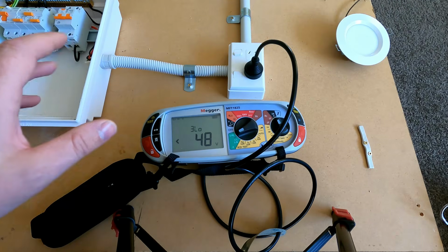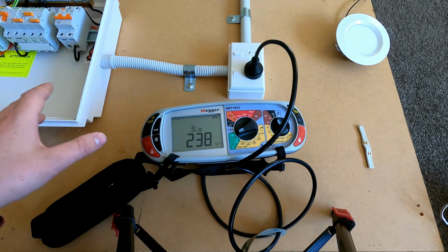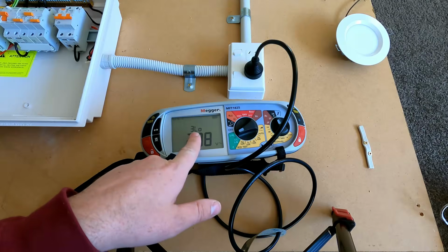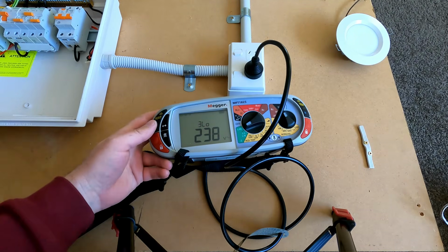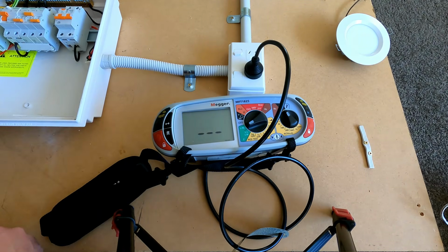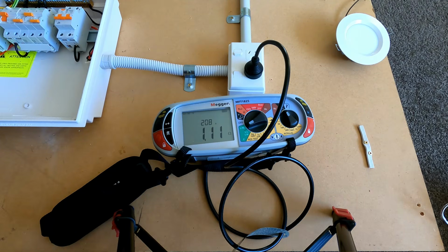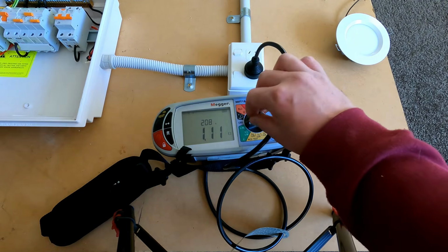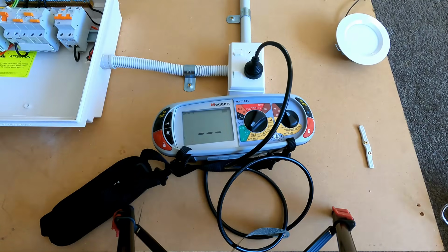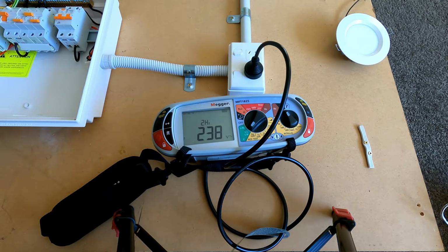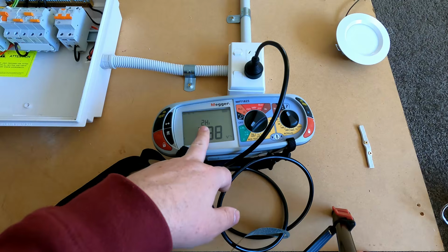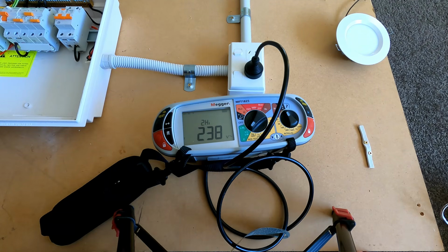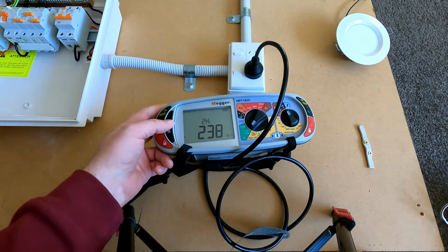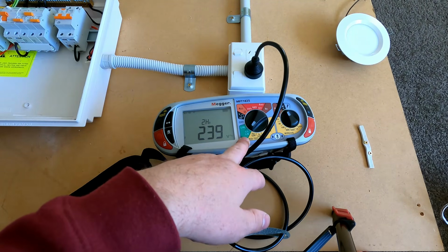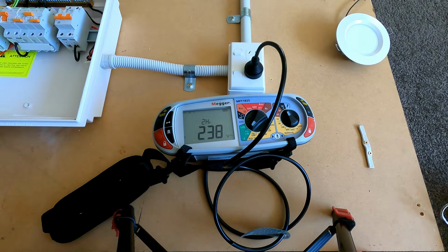Now this one here, because it's on the load side of the RCD, it will have to be your 3-lead low current test, which is default, and hit test. 1.11 ohms, 208 amps. Then we put it on line to neutral. Now line to neutral test is always your 2-lead high current test, because it's the most accurate and fastest test you'll be able to do. You can't change it. The high current test on the neutral is not going to trip your RCD.